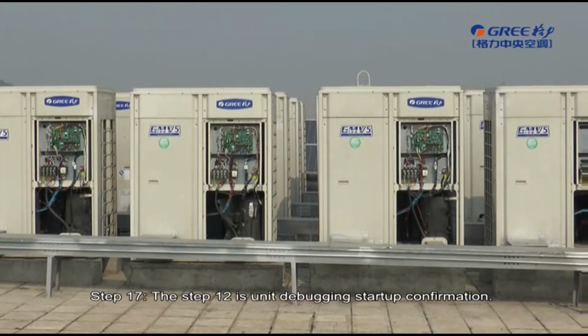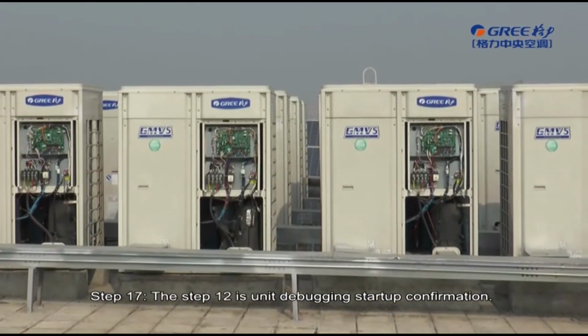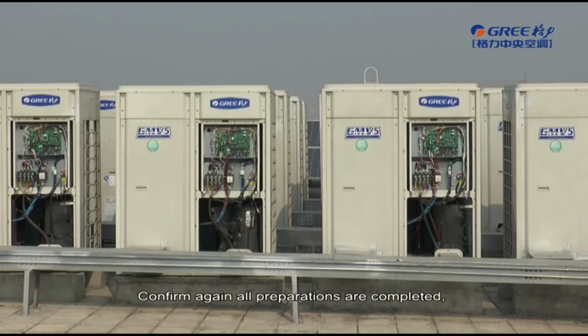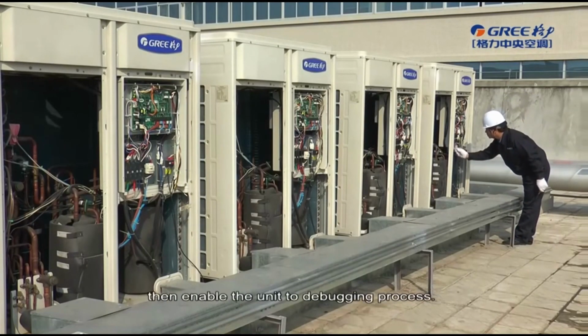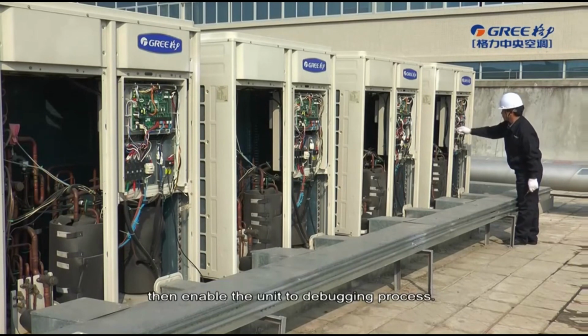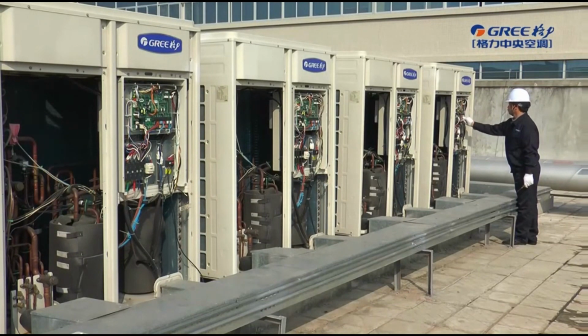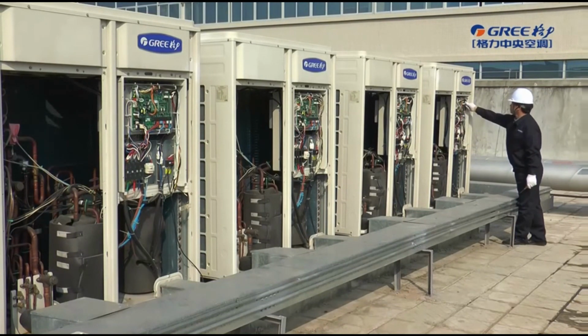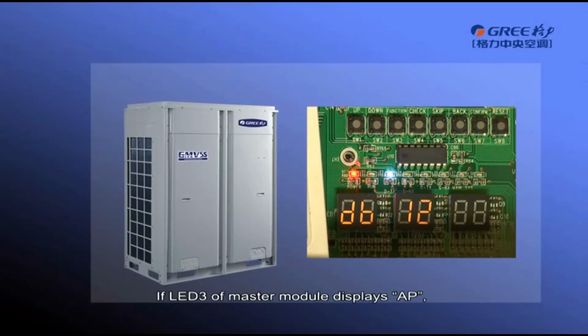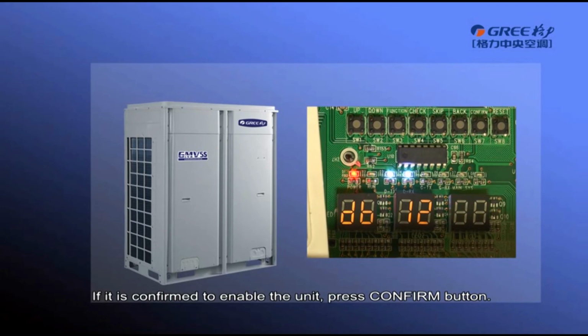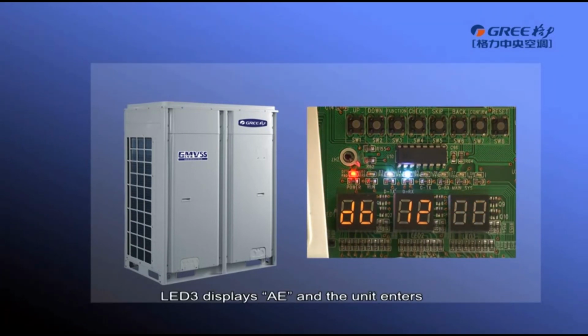Step 12 is unit debugging startup confirmation. Confirm again all preparations are completed, then enable the unit to debugging process. If LED 3 of master module displays AP, it indicates that the unit is waiting for enabling confirmation. If it is confirmed to enable the unit, press confirm button. LED 3 displays AE and the unit enters step 13 automatically.